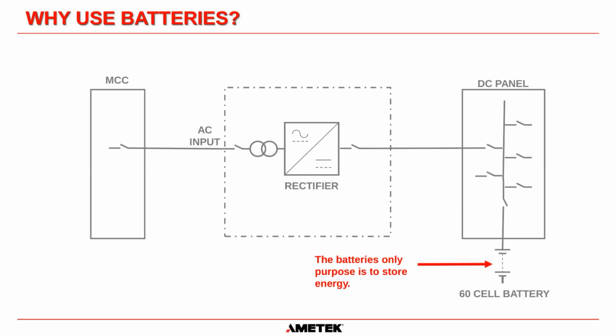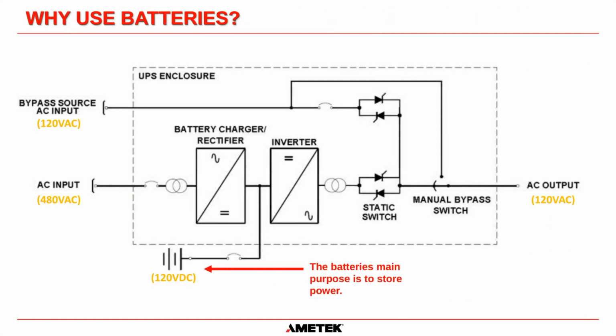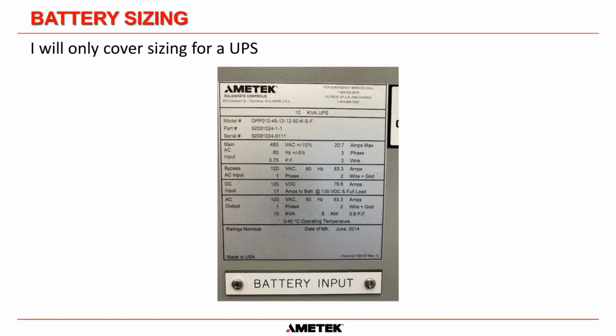So it's very important that the only purpose a battery has in a UPS system or a DC system is usually to store the energy. Okay, like I said, in a UPS, its main purpose is to store power. So if we do lose AC input to the UPS, then the batteries will carry on supplying the inverter with the DC power that it needs to convert it back into AC. So therefore, we need to know how to size the batteries. We need to know what battery to buy to get the time that we require for that particular system. So I'm only going to cover battery sizing for a UPS because we're a UPS company, and it's just what we do on a regular basis.